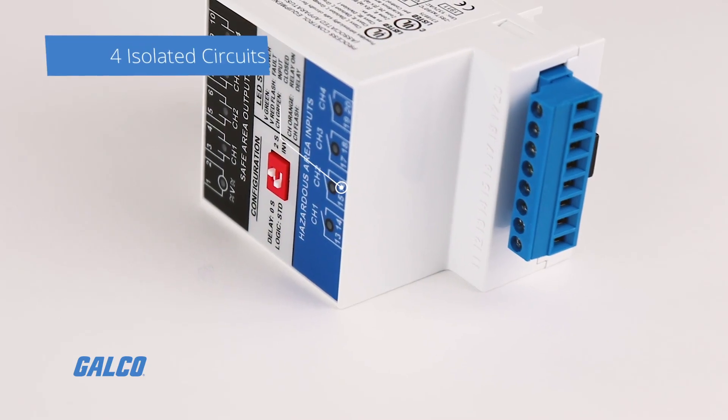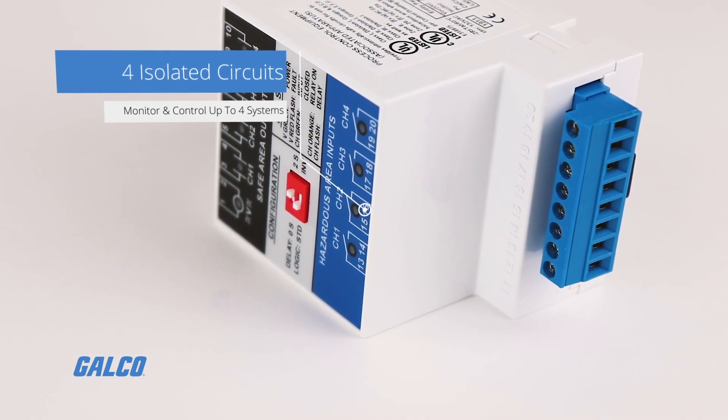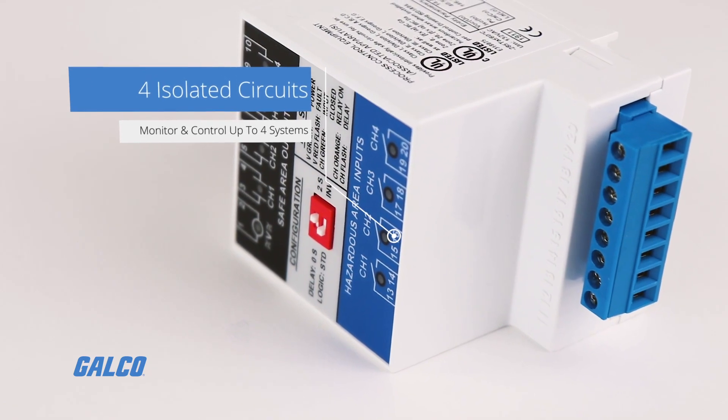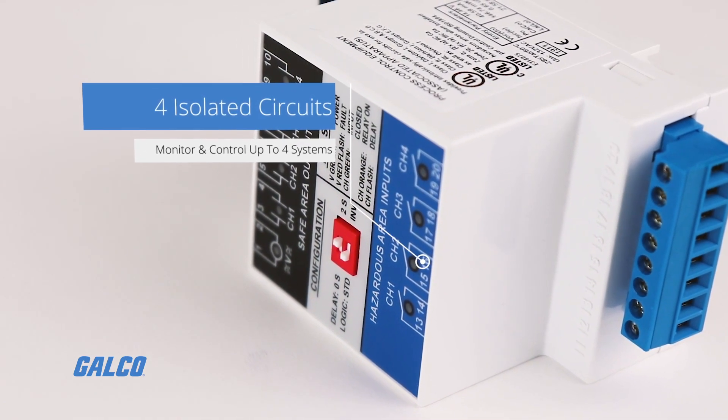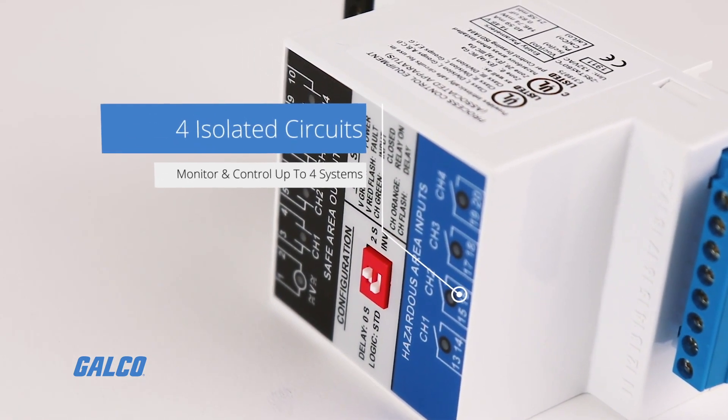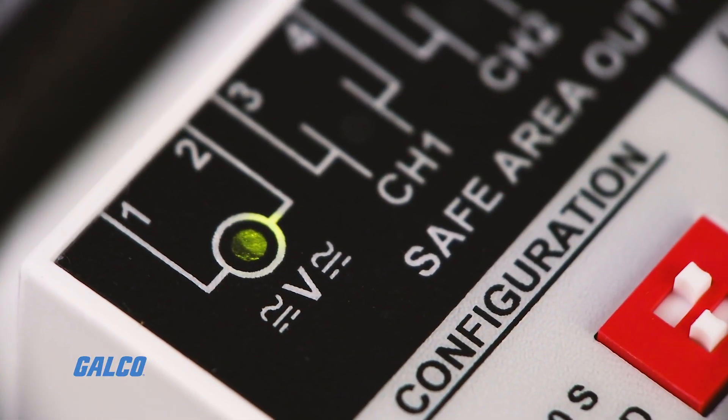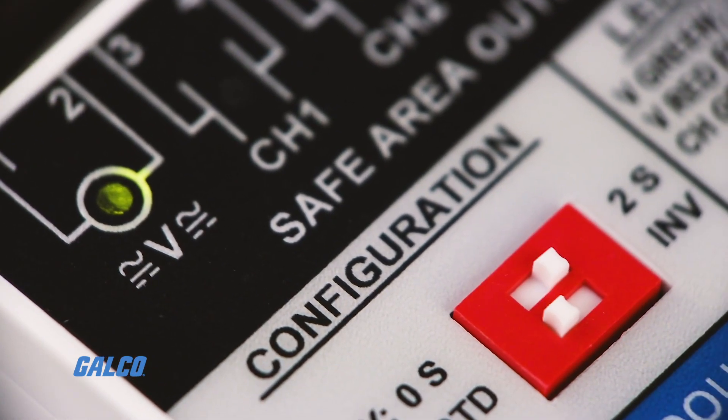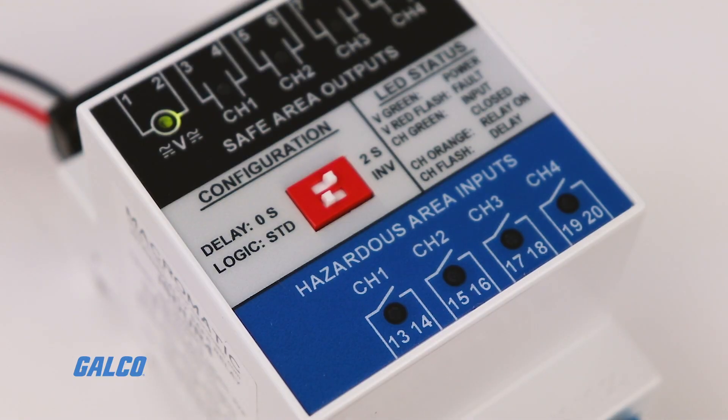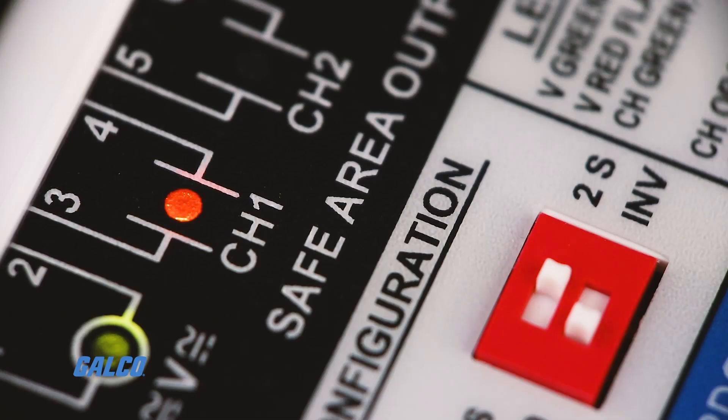Each ISD series product consists of four intrinsically safe inputs and four corresponding electromechanical relay outputs. With voltage applied, the VLED will illuminate green. When the input device is closed, the input LED will illuminate green. When the output relay is energized, the output LED will illuminate orange.